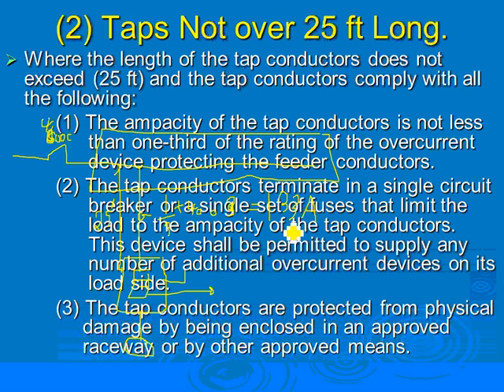You don't go up. You have to go down. What's the lower size from 133? Thank you, 125. That's another thing. When you tap conductors, you can't go up on them. So I have my overcurrent protection device has to be 125 because I don't have 133.